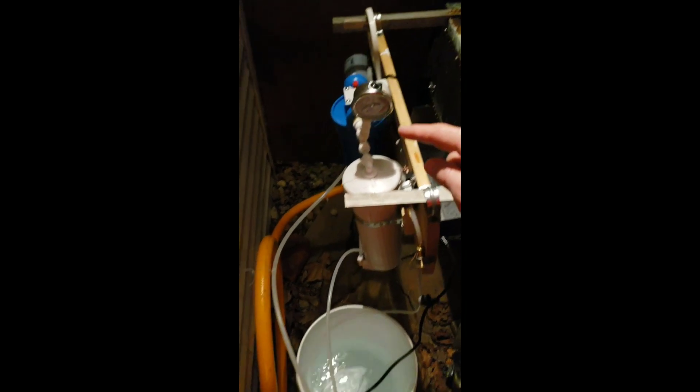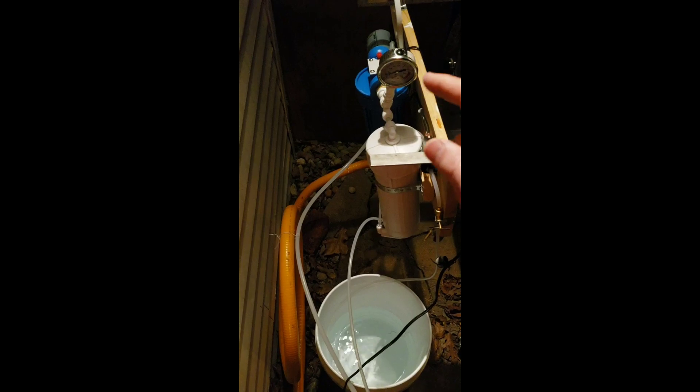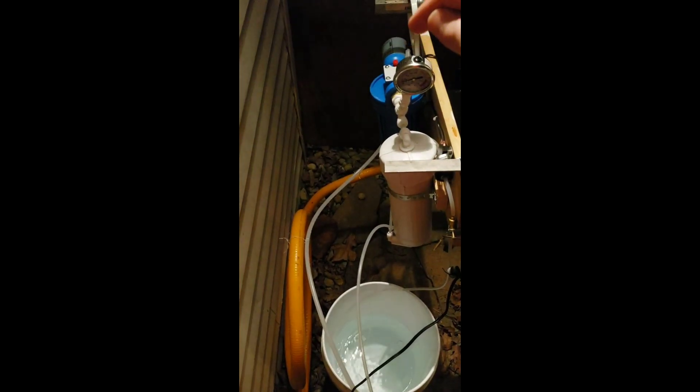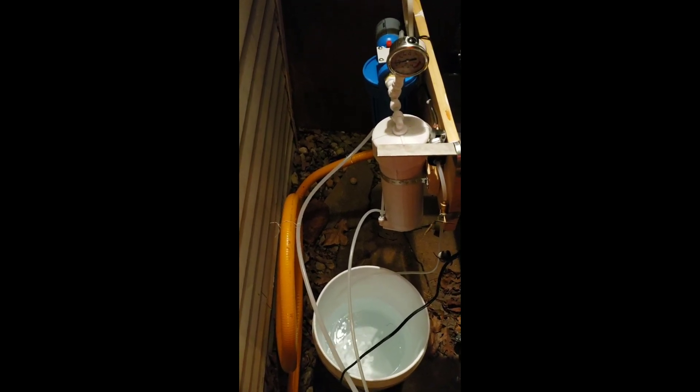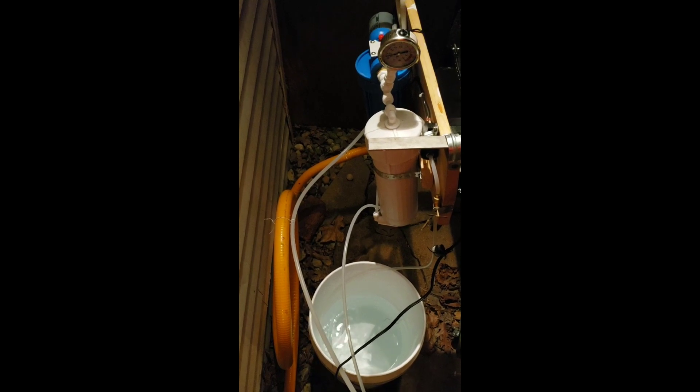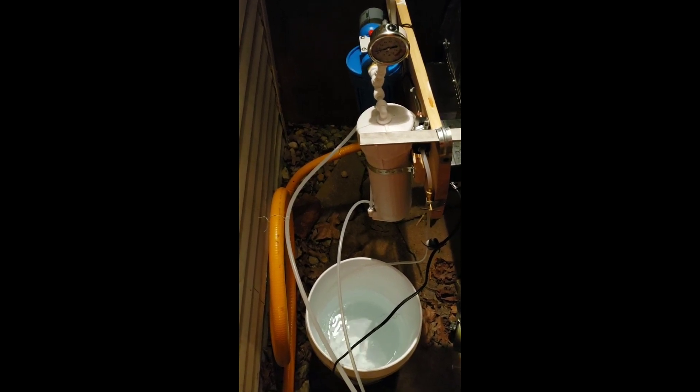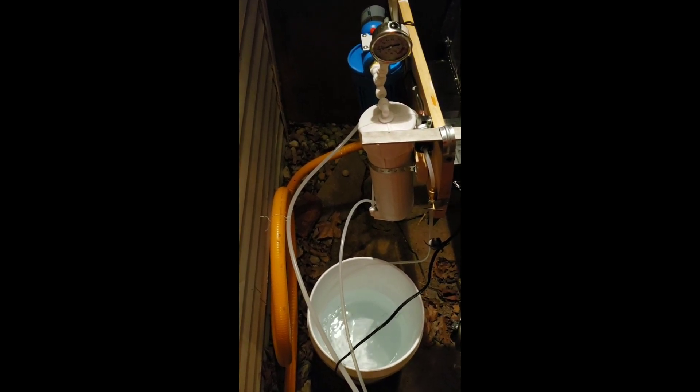Then you're going to take your intake that goes into your pump over on the other side of the RO. That's going to get dropped into your permeate container or your tank. That's going to be your inlet, and you're going to use that permeate to flush the RO membrane.